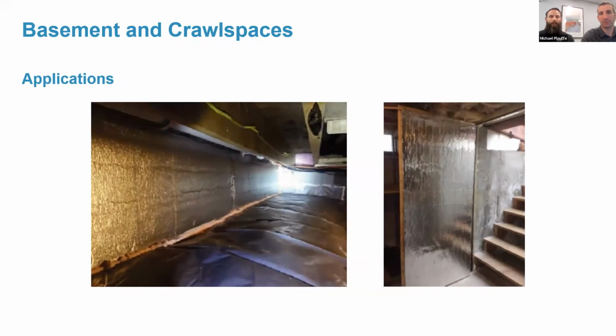I mentioned bulkheads. Here's a good example of a wooden bulkhead door, which was retrofit with a piece of foam board insulation and had weather stripping applied to reduce heat loss. This is a pretty significant hole in the building shell, where this bulkhead stairway is. Sometimes there might not even be a door there to begin with, so something could be fabricated to insulate and seal that opening.